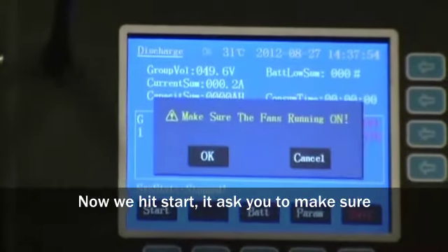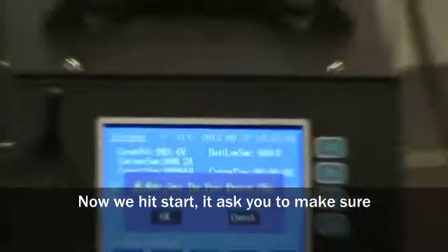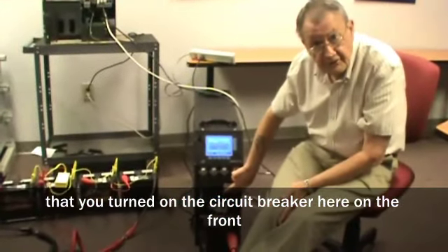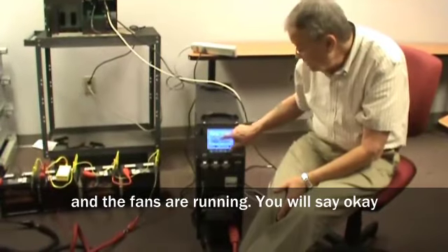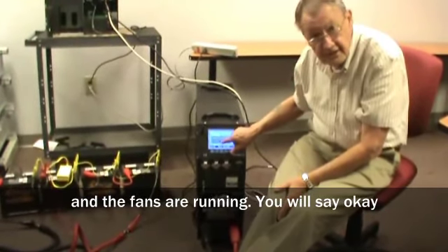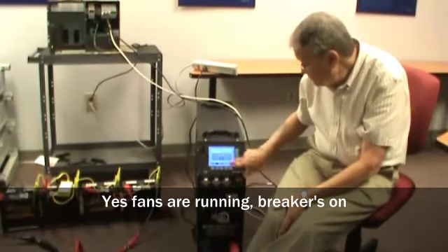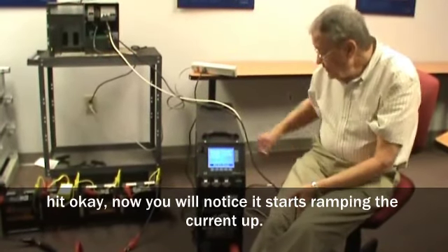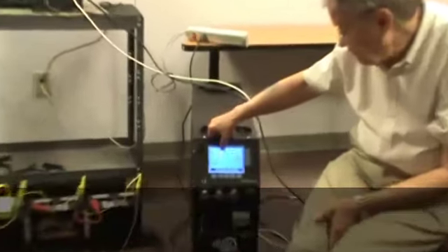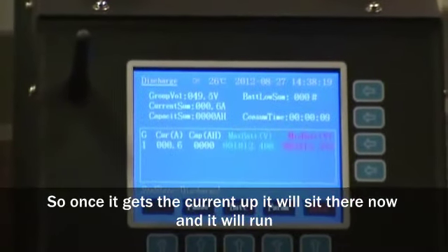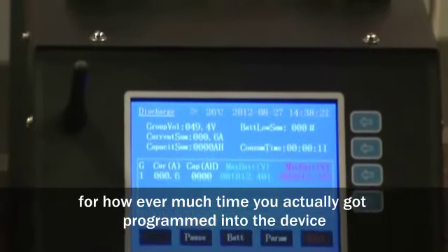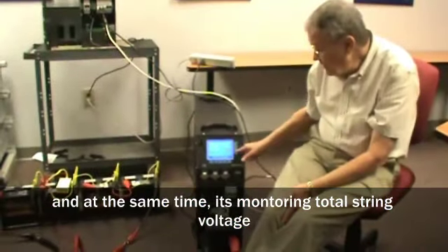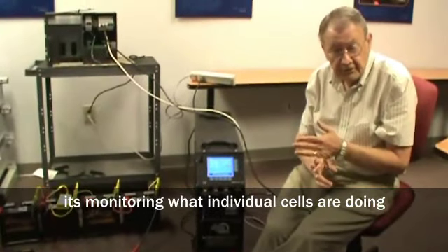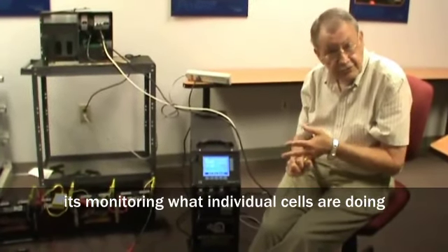Now we hit start. It asks you to make sure that you turned on the circuit right here on the front and the fans are running. You would say, okay, yes, fans are running, breaker's on. You would hit OK, and now you'll notice it starts ramping the current up. Once it gets the current up to 1 amp, it'll sit there and run for however much time you've actually got programmed into it. And at the same time, it's monitoring total string voltage, it's monitoring what each individual cell is doing.